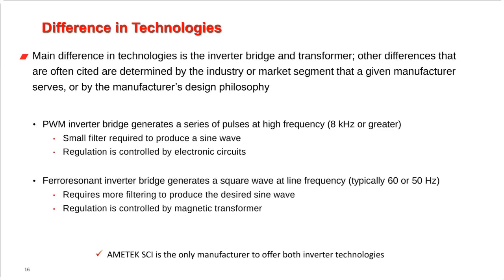And a lot of people don't get this idea in their head. So for a PWM inverter, for a modern day electronic inverter, all the control is done by control boards, logic, communication, CAN buses, fiber optics. There's a lot of stuff going on to create that high frequency switching for an inverter. And all the voltage controls and current controls are done through control board logic. For a ferro-resonant inverter, all of the regulation is done by the transformer.